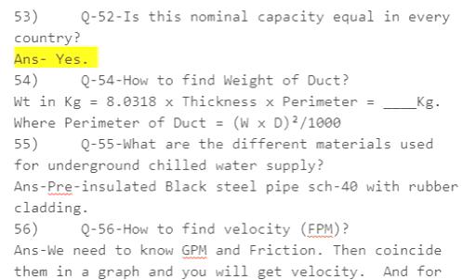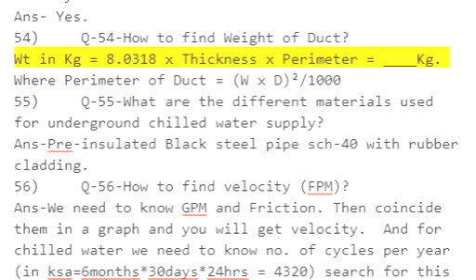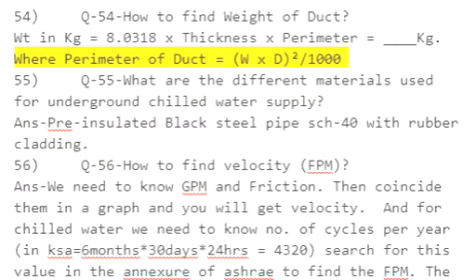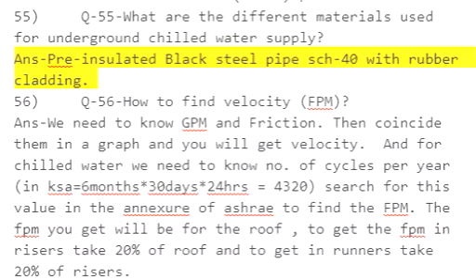Q54: How to find the weight of ducts? Weight in kilograms equals 8.0318 multiplied by thickness multiplied by perimeter — where perimeter of duct equals (W + D) multiplied by 2, divided by 1000. Q55: What are the different materials used for underground chilled water supply? Answer: Pre-insulated black steel pipe schedule 40 with rubber cladding.